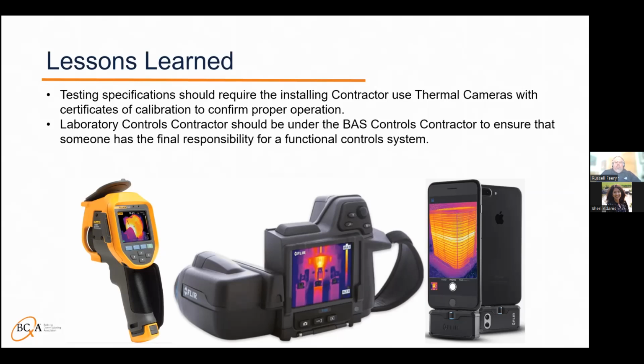Another thing to keep in mind is that you could rent these if you're not in a position that you're willing to invest. Just from the sheer volume, we had over 1,500 chilled beams between 3 projects, so it made sense for us to just purchase it. But there are costs involved with keeping that calibrated and certified at a minimum of $600 a year. And hopefully you don't need any repairs, which can be more pricey during the calibration effort.